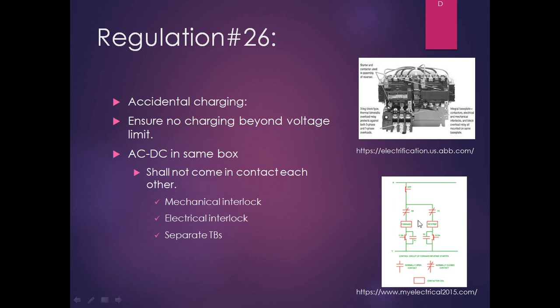Here what we do, we use the NC contact of one contactor in series with the coil of the other contactor. It ensures that unless one contactor is de-energized, the other one will not energize, and vice versa. If somebody energizes one, that will ensure that the other contactor is de-energized. Also, AC and DC should be used in separate terminal boards. They should not be taken into the same terminal boards.